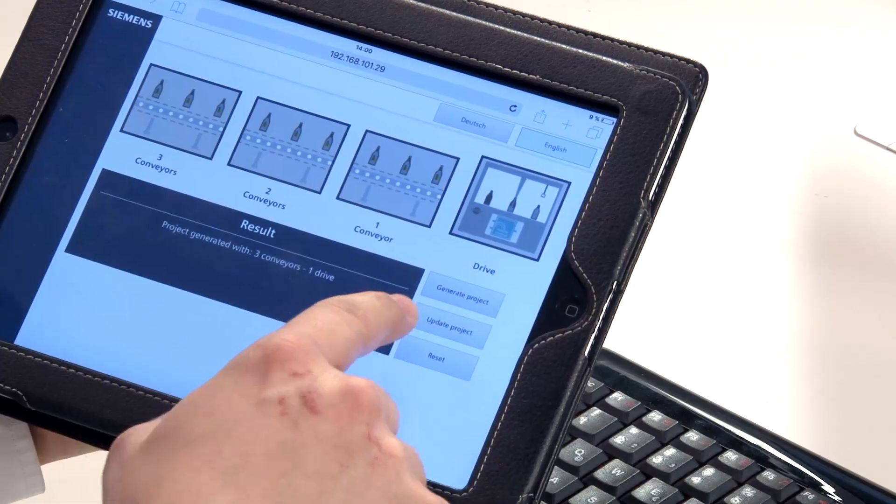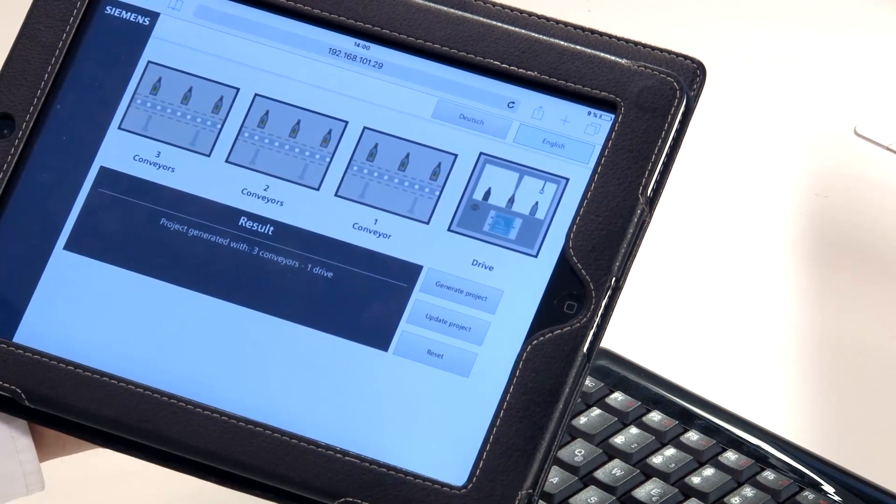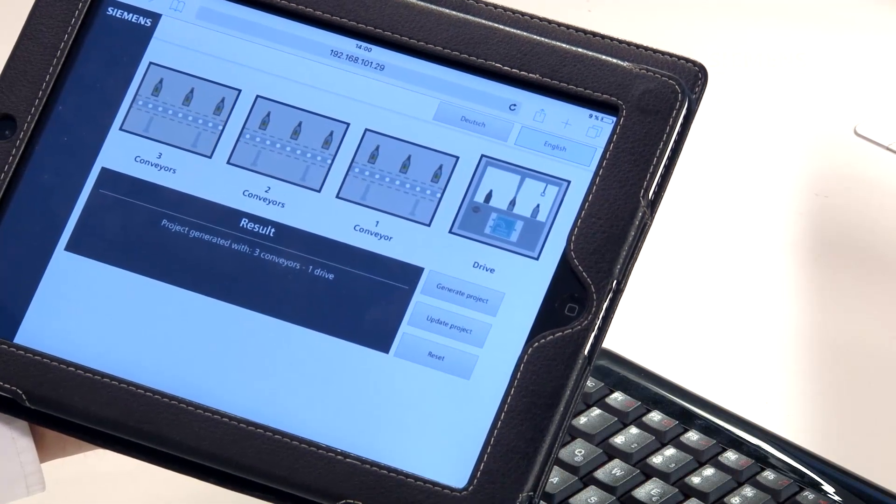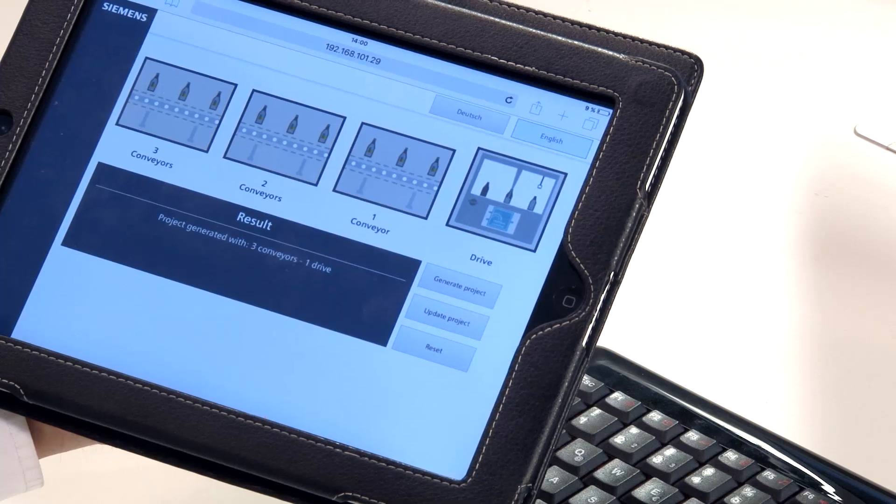This block is versioned as 1.0.0. If a new version of this block is produced, in the event that an error has been detected by another user during the commissioning process, that user can save it back to the company's server via the global library, allowing us to update this function block again. This is done via the Update Project button, which opens a global library on our computer, then performs an update on our project.